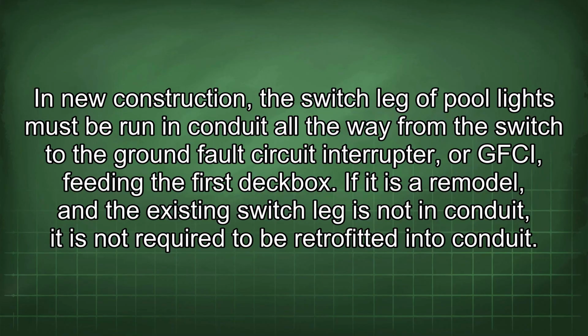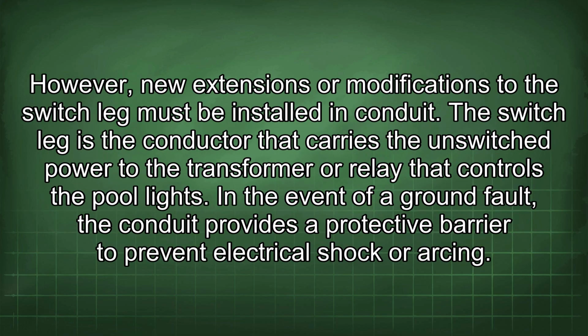In new construction, the switch leg of pool lights must be run in conduit all the way from the switch to the ground fault circuit interrupter, or GFCI, feeding the first deck box. If it is a remodel and the existing switch leg is not in conduit, it is not required to be retrofitted into conduit. However, new extensions or modifications to the switch leg must be installed in conduit.